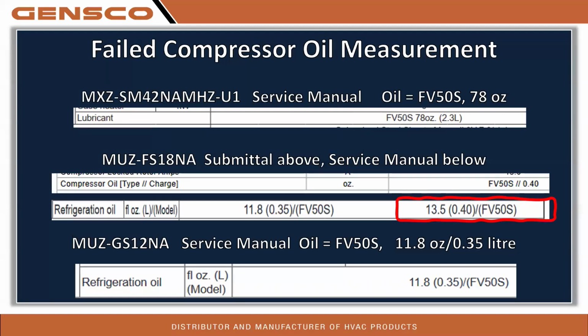So that's the kind of oil you should be getting out of these compressors. And if you get nothing, then that oil is still out in the system. And if that oil is still in the system, especially that Smart Multi with 78 ounces, if you just put a new compressor in there, which is going to get you a new 78-ounce oil charge, now you have 156 ounces in the system. That could lead to another failure. The odds of you losing a second compressor after you lose one go up 400% from a brand new unit failure rate.